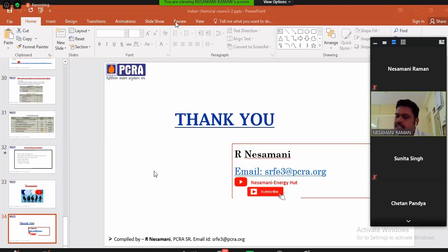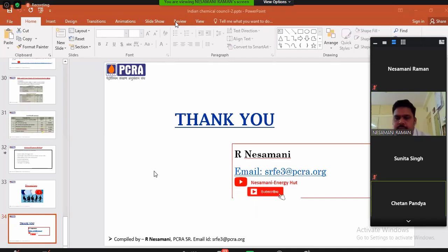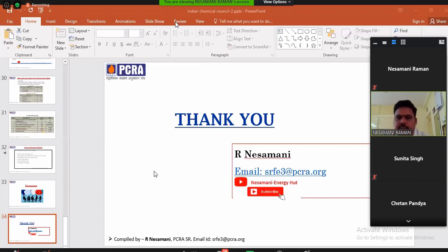Okay, 160 degrees Celsius. Water only, no? Yeah, we are getting water only. Do you add that into the feed water loop again? Yeah, we have added it in the feed water tank. Okay, then it is good. Then you are not wasting, because if you are adding that into the loop without losing much energy, then we cannot say that you are losing, if the pipelines are insulated, no? Yeah, exactly. Then it is fine, sir.